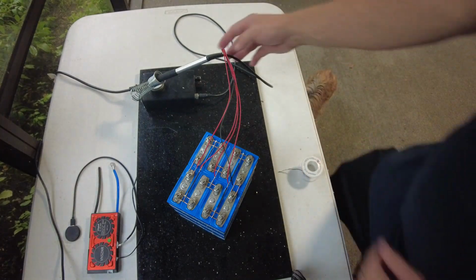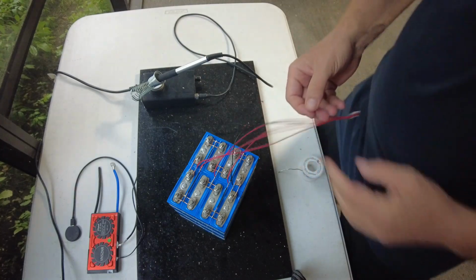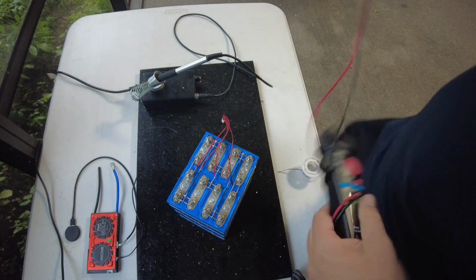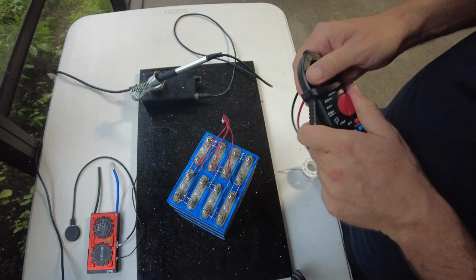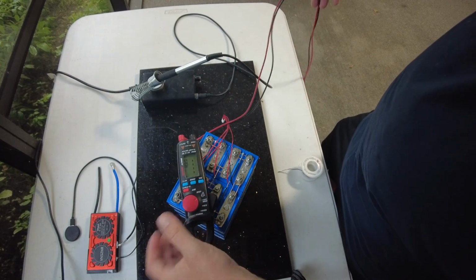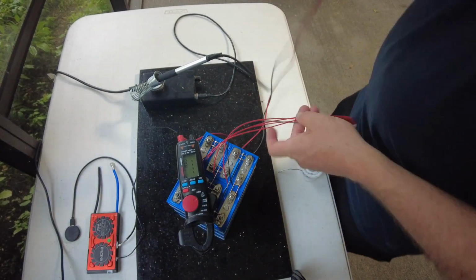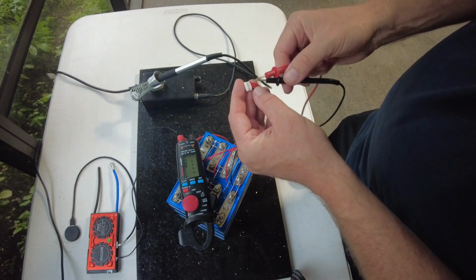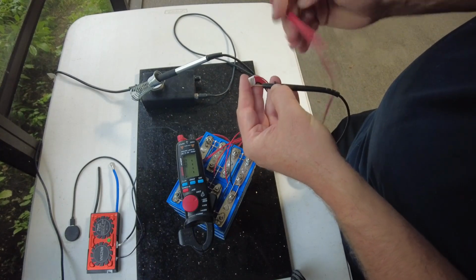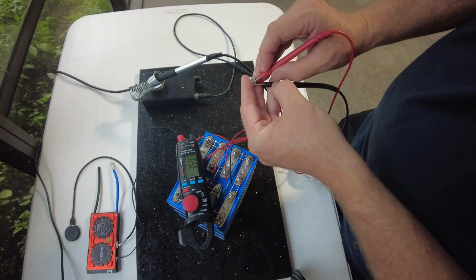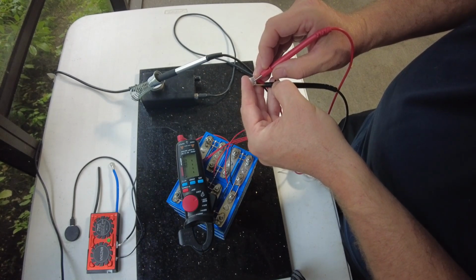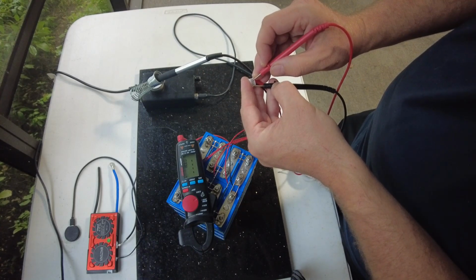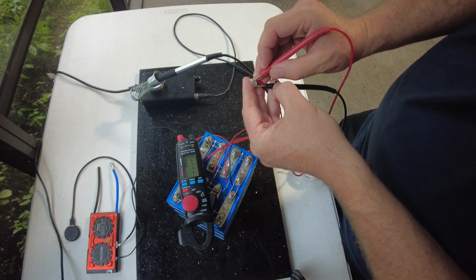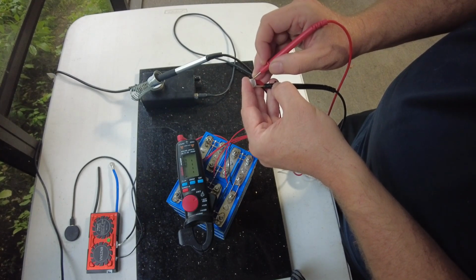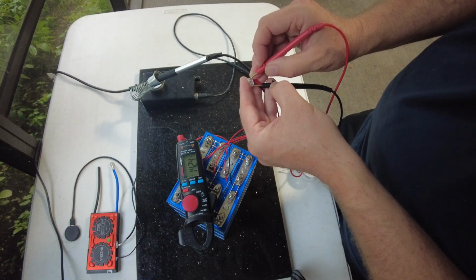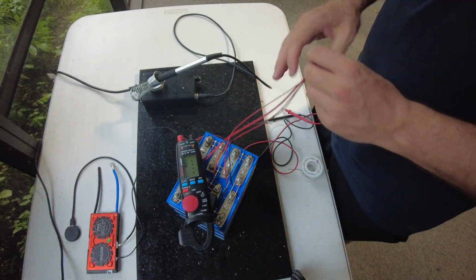So you can actually use a meter to test that these wires are correct. Most negative, the next one to it should be 3.5, okay, and then we should see like 7, yep, and then we should see 10, yep, 10.72, and then 13 something, or 14, yeah, 14.25, yep. So they're all connected properly.